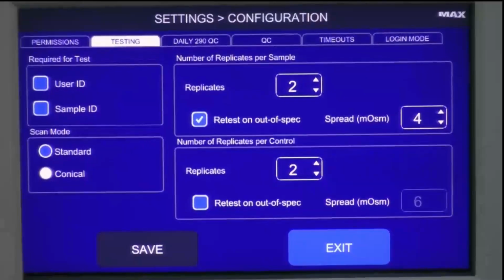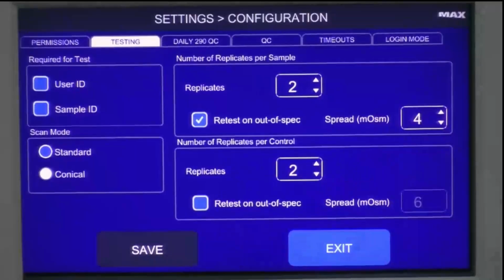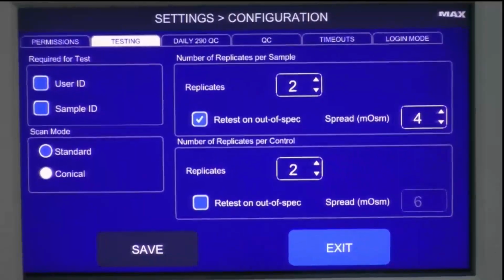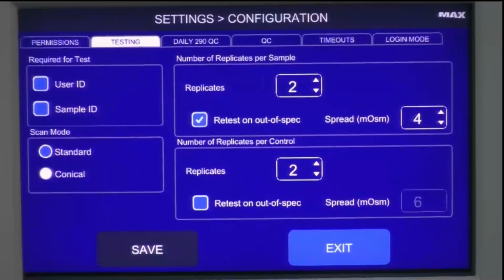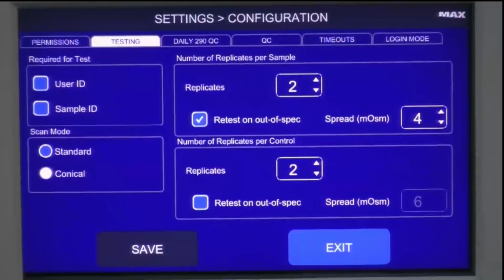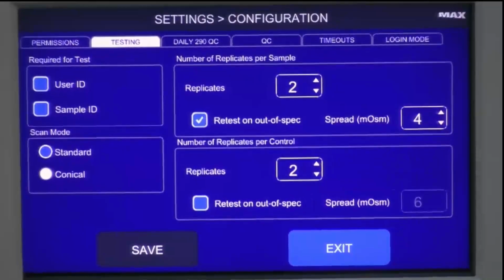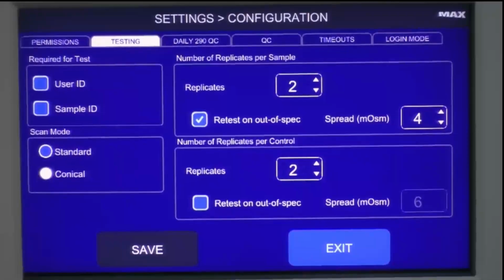And if the spread between those 2 samples is greater than 4 milliosmoles, do it again. So that will actually take a result that is outside of a specific spread, and after running a 3rd test, identify the outlier, and then only cross over the 2 results that are most closely associated to your LAS. So a really cool feature as well. You can do the same thing down at the bottom there for your controls. If you want a certain spread between 2 tests that are run on the same control standard, you can set that there as well.